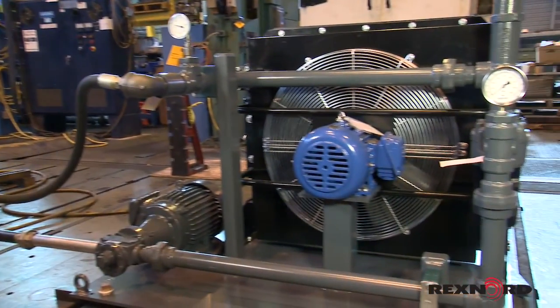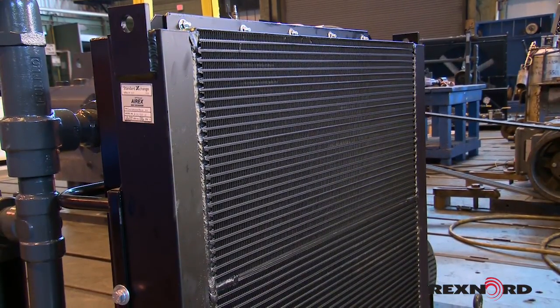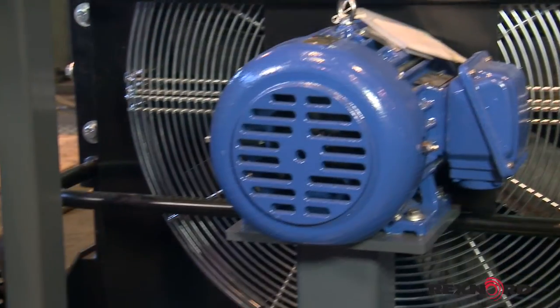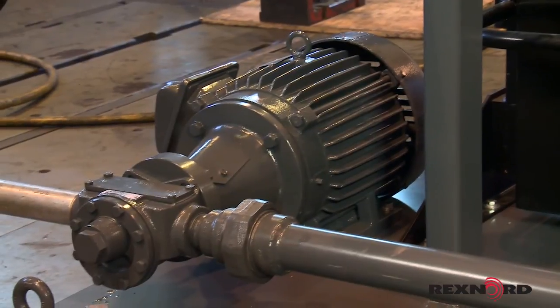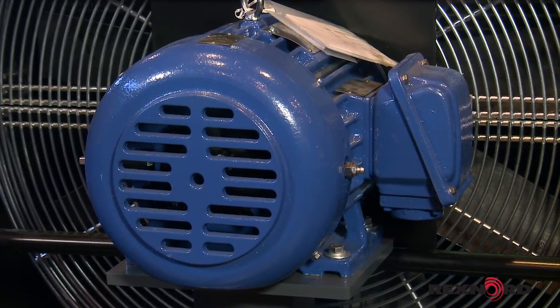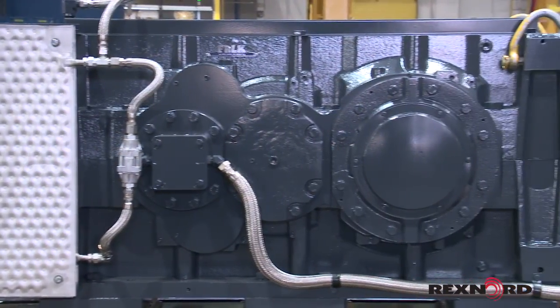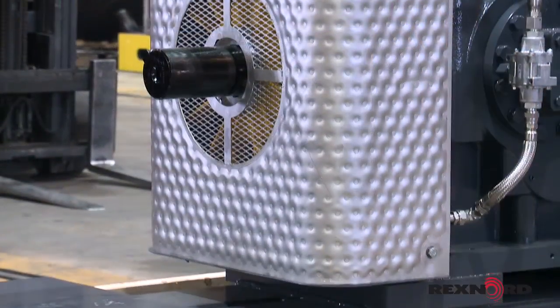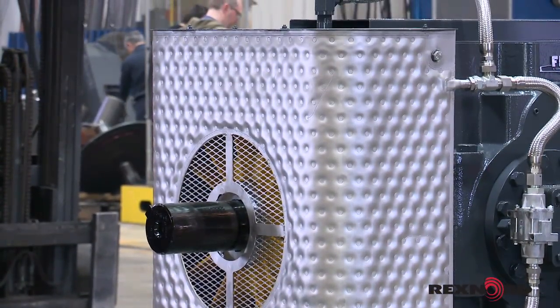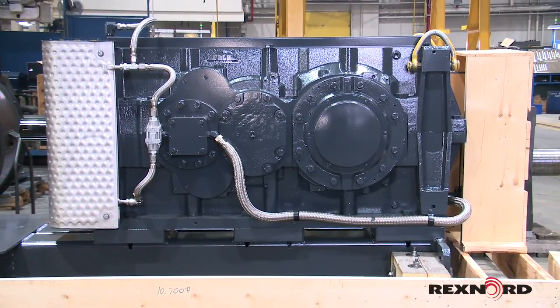A conventional cooler, however, tends to have a delicate heat exchanger, similar to an automotive radiator, making it much more susceptible to damage and clogging. The conventional radiator also has its own electric motors to power the oil pump and fan. In addition to being potential points of failure, these components require additional electrical wiring and equipment, separate from the power supply for the main motor. This increases cost and reduces reliability of the system. Although optimized through advanced technology, the DuraPlate system is simple, minimizing parts and maximizing reliability. And finally, the stainless steel components of DuraPlate will have a long operating life, even in corrosive environments.